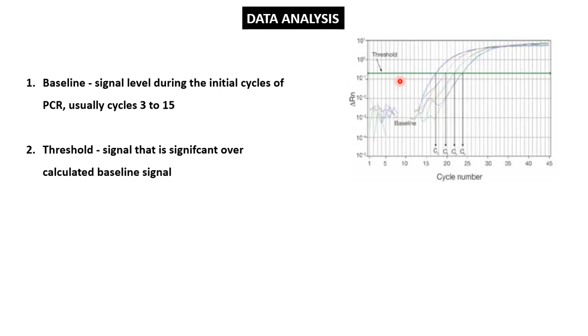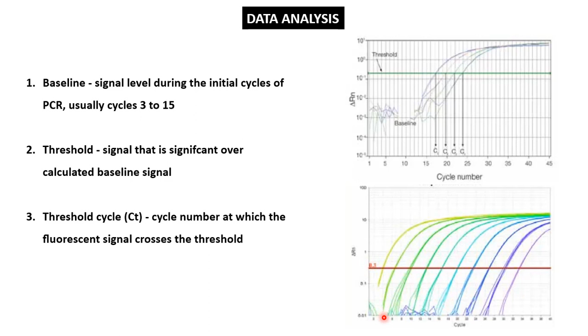Next is the threshold cycle. The point of amplification which touches the threshold is the threshold cycle. Or in other words, it is the number of cycles required for fluorescent signal to cross the threshold or exceeds the background level. Determination of CT value is the prime objective of the real-time PCR and indicates what concentration of target DNA was present in the sample. As I said earlier, lower the CT value means high concentration of DNA was present in the sample and vice versa. These different lines shows amplification for different samples, and the sample from this yellow line contains the highest concentration of DNA than others. That is how we quantify the DNA.